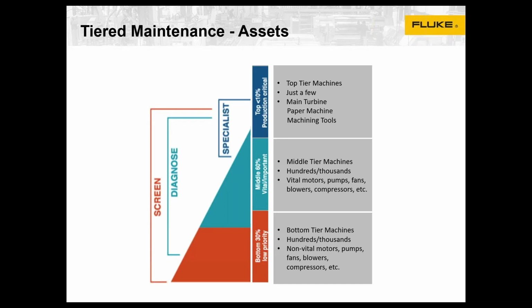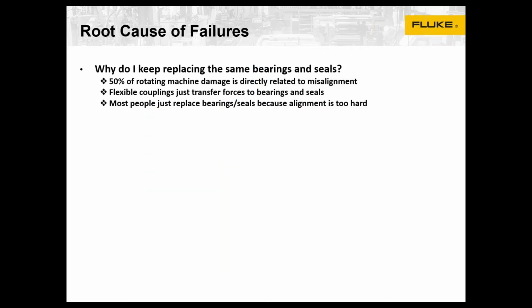Another thing that you can use is on-site knowledge on how these assets fail, what's a typical failure mode? So part of that criticality survey is to identify failure modes. The example of that I used before is that we keep fixing the same problems over and over. We see that a lot with bearings and seals on pumps, rotating equipment. Well, maybe the situation is you have an underlying root cause that you're not aware of, and about 50% of the issues, the premature damage to bearings and seals, is really caused by a condition of misalignment. So all the forces are still there, even if you have flexible couplings, all the forces from misalignment are still there, and they're transmitted to the bearings and the seals.